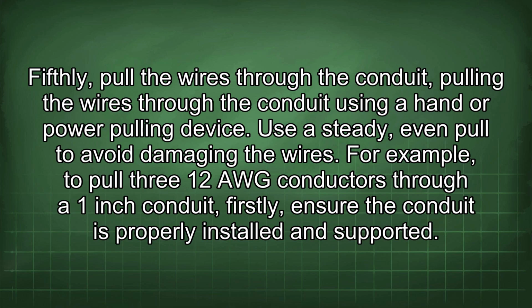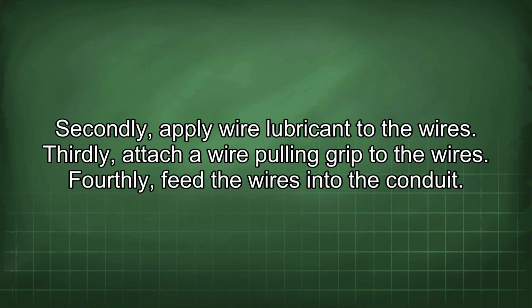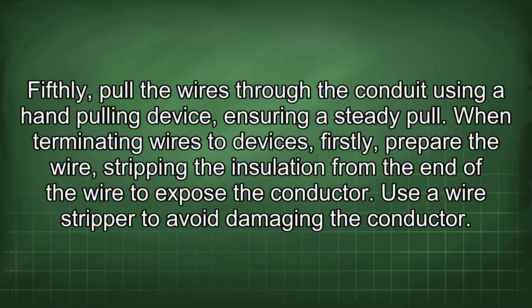For example, to pull three 12 AWG conductors through a 1-inch conduit, firstly, ensure the conduit is properly installed and supported. Secondly, apply wire lubricant to the wires. Thirdly, attach a wire pulling grip to the wires. Fourthly, feed the wires into the conduit. Fifthly, pull the wires through the conduit using a hand pulling device, ensuring a steady pull.